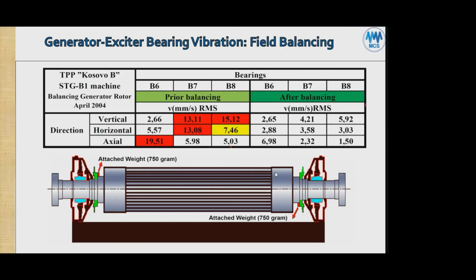So the magnetic forces are going to be different than a thermal unbalance inside the rotor or inside the stator, because they will typically be caused by non-centering of the rotor in the stator. As it is non-centered in the stator, it not only develops a 1x, but it also develops a 2 times vibration frequency. You're going to get a 2 times vibration effect when there's a magnetic unbalance force, and not only a 1x. The exact magnitude of the 2 times will depend on the load, for one, and it will depend on the bearing damping ability and other factors. But there'll be much more 2x vibration that will be electrical.